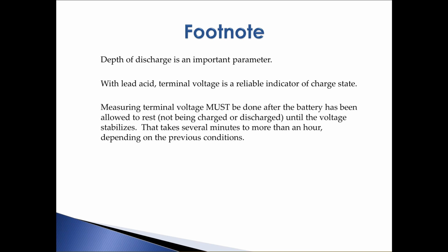What you must remember is that the terminal voltage in those charts is measured after the battery has been allowed to rest—not charged or discharged—until the voltage stabilizes. There's a surface charge effect in lead acid that raises terminal voltage, and it can take anywhere from several minutes to more than an hour to dissipate, depending on previous charge or discharge conditions. Without doing that, the measurement is essentially useless, because you'll be measuring the surface charge, not the actual battery voltage, and without knowing the true voltage, you don't really know the state of charge.